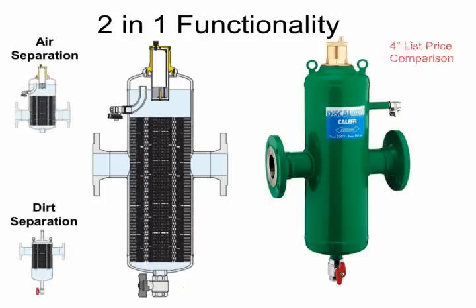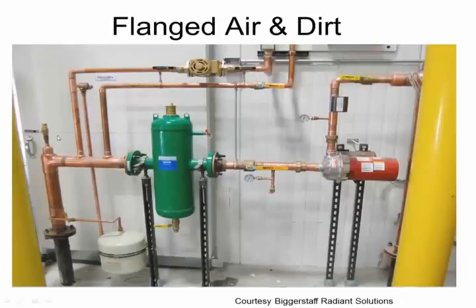So rather than specify two components doing each function separately, from strictly an economical standpoint, if you look at our list prices of a 4-inch line as an example, your 4-inch air separator is listed at $4,200, $3,600 for the dirt separator. The combined one will do the same job for less than $5,000. So not much of a premium over just the air separator itself.